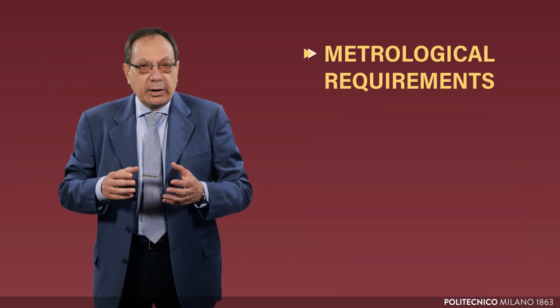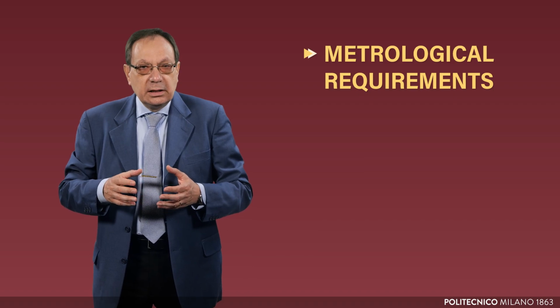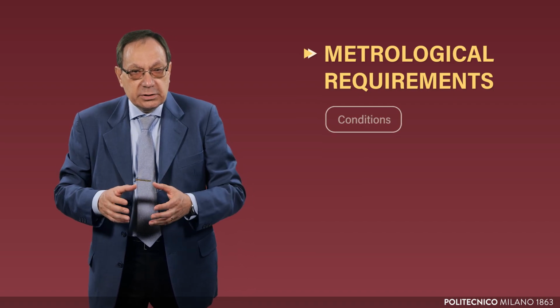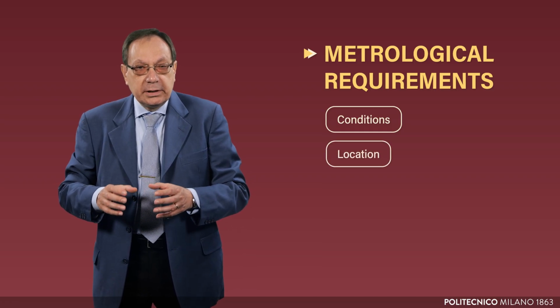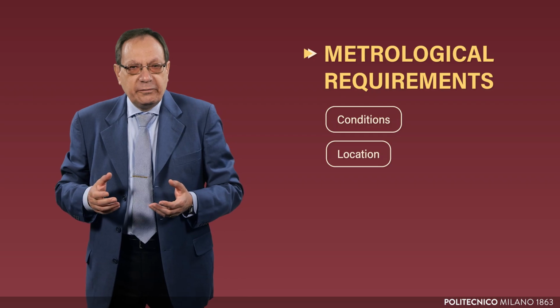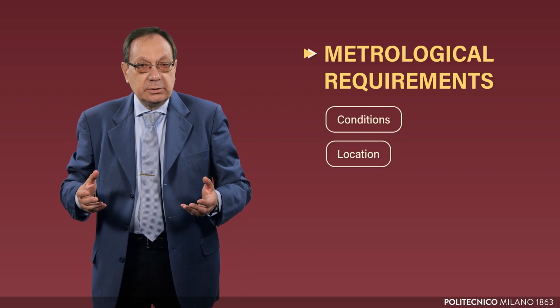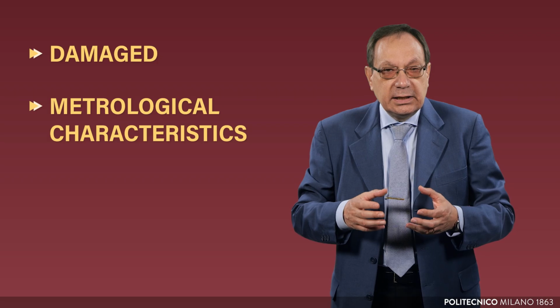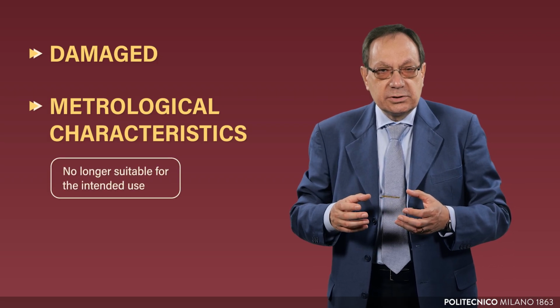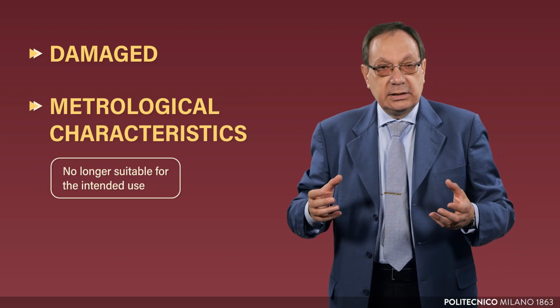To guarantee the metrological requirements for the intended use, strictly speaking, one should carry out a calibration under the conditions and at the location of use before employing the measuring system. It is clear that this way of proceeding is so expensive as to be impracticable. On the other hand, it cannot be excluded, even if it is unlikely, that the result of the calibration may cease to be valid immediately after the calibration has been carried out. For example, if the instrument is damaged in a way that is not immediately visible during shipping from the calibration laboratory to the place of use, its metrological characteristics may no longer be suitable for the intended use, even though the calibration results indicate otherwise.